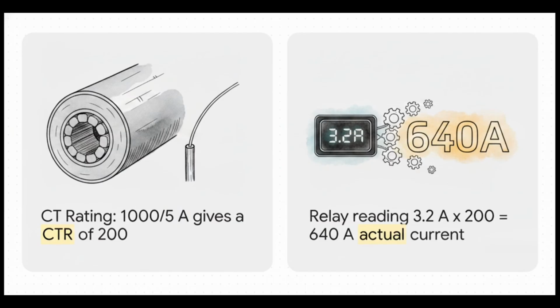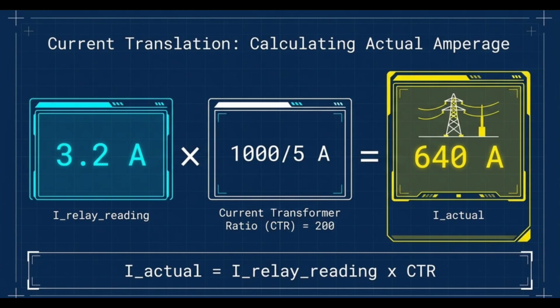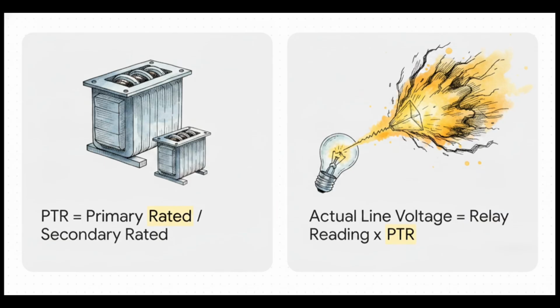Say you've got a transmission line with a CT rated at 1,000 over 5 amps. That gives us a CTR of 200. Now, if the relay in the control room is comfortably and safely reading just 3.2 amps, it simply multiplies that 3.2 by the ratio of 200. Suddenly, the system realizes that a massive 640 amps are actually surging through the primary line right outside. Okay, let's flip over to the voltage side.